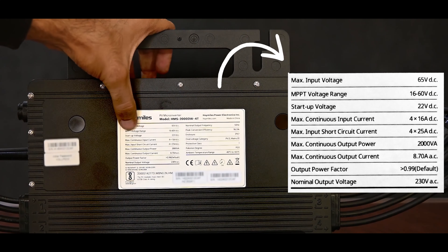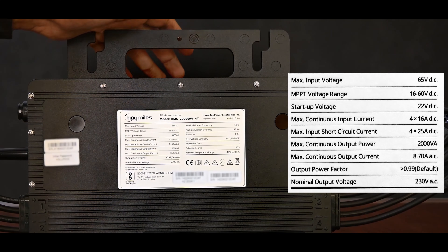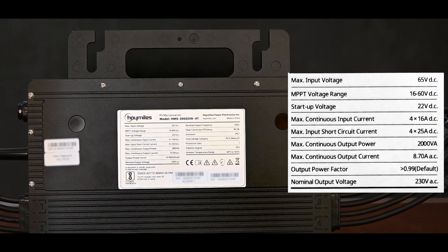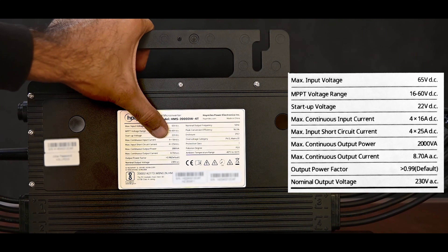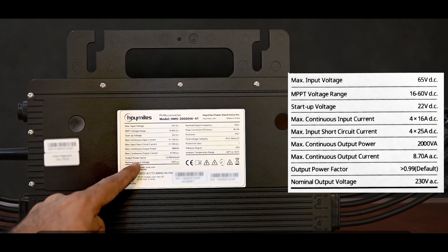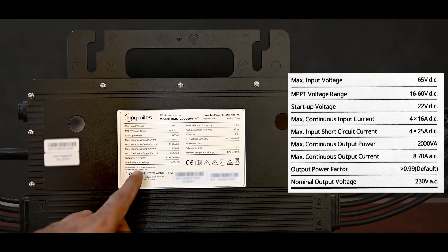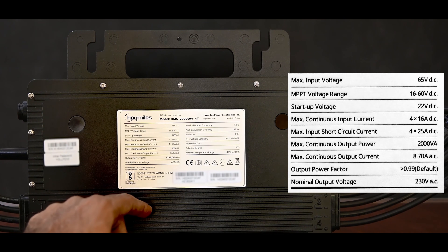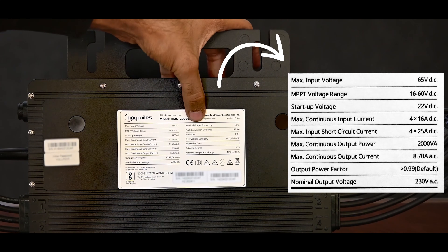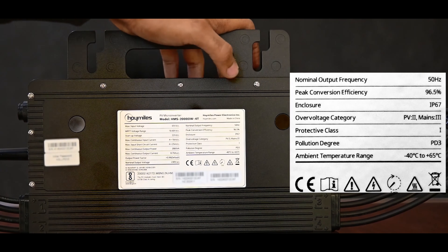Its max input voltage range is 65 volts. The MPPT voltage range is from 16 to 60 volts, meaning you can connect panels with a VOC from 16 to 60 volts — even a 500 to 600 watt panel will have no problem. Its startup voltage is 22 volts. Its max continuous input current is 4 × 16 amperes, supporting 16 amperes per panel, and the input short circuit current is 25 amperes. Max continuous output power is 2 kVA. Max output current is 8.70 amperes AC, nominal output voltage is 230 volts, power factor is 0.99, and output frequency is 50 Hz. Its peak conversion efficiency is 96.5% and IP rating is IP67, so it is fully protected from dust and dirt.